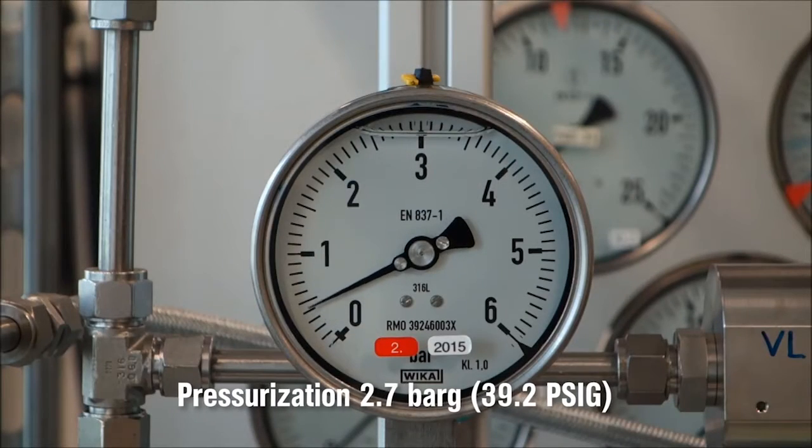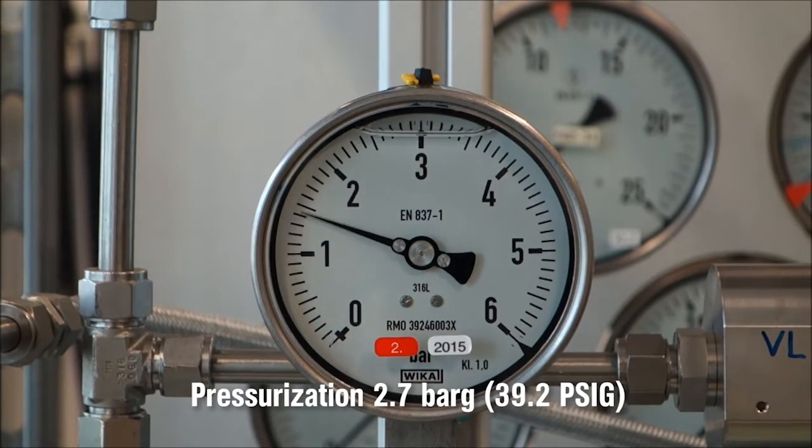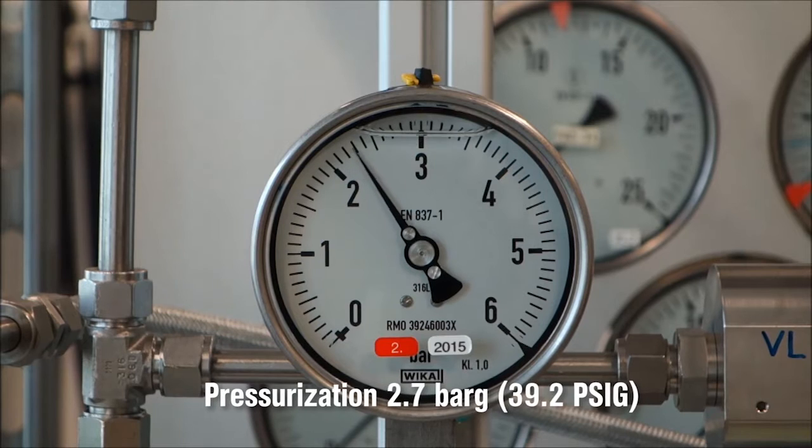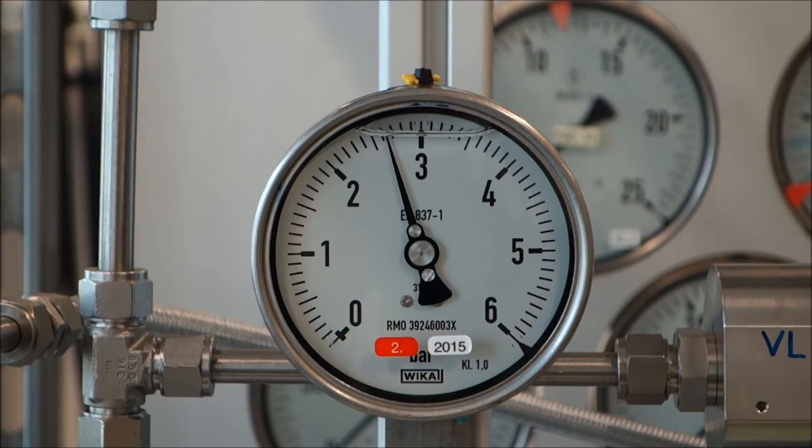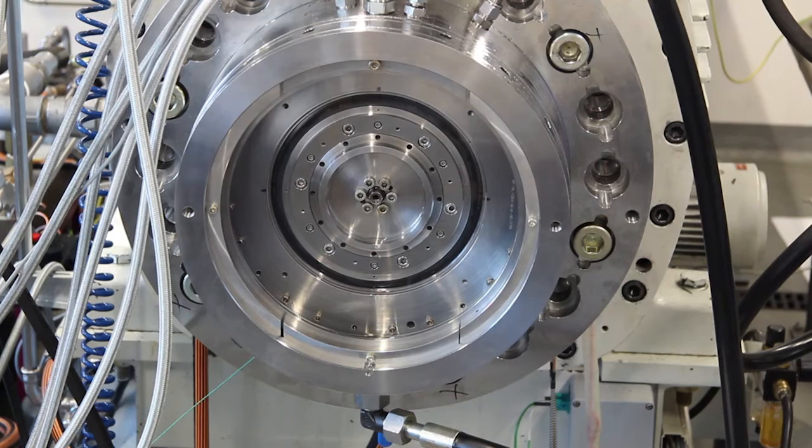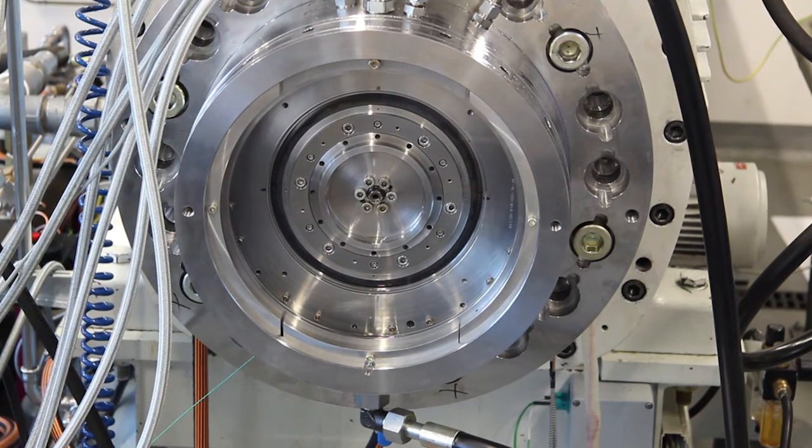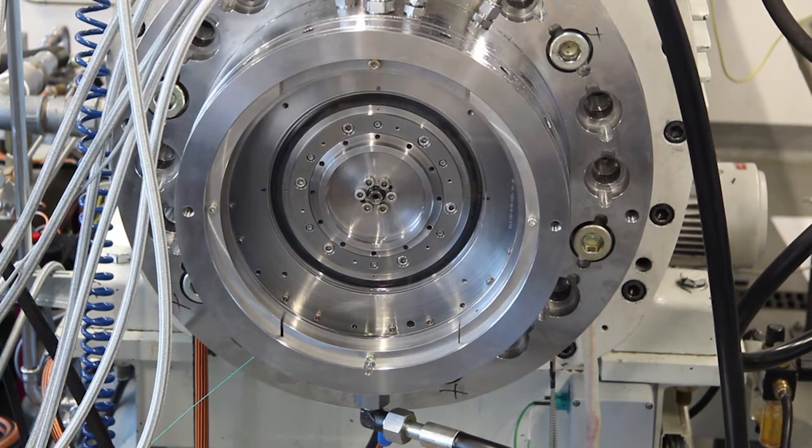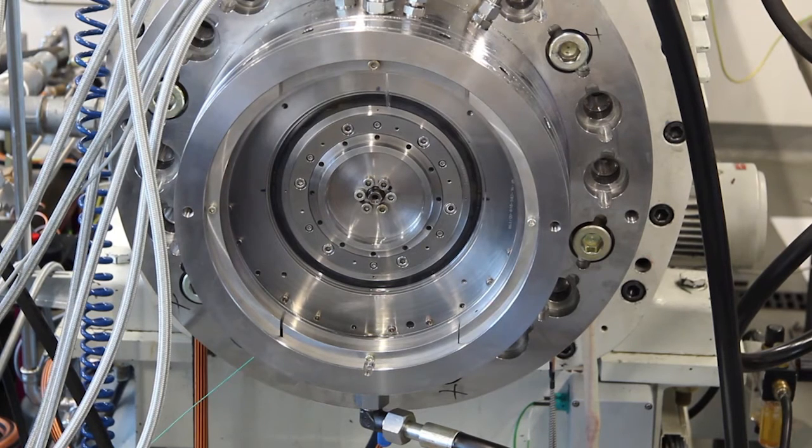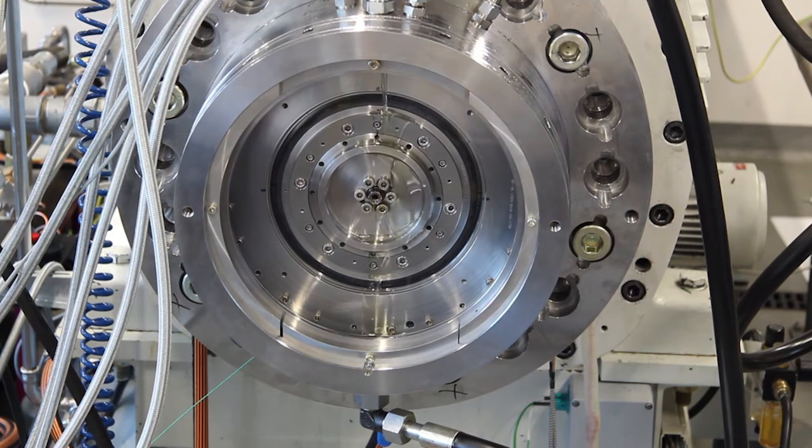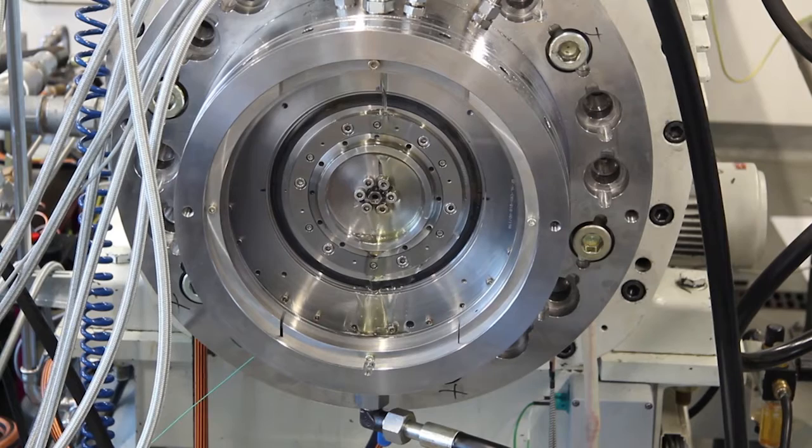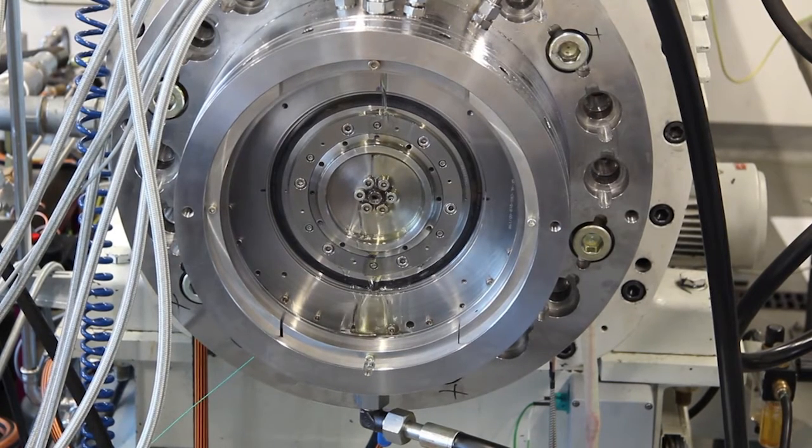The seal first undergoes a dynamic run under normal operational conditions. The processes in the bearing oil housing can be observed through an acrylic glass window. The system is pressurized to 2.7 bar gauge, which is equivalent to 39.2 psi gauge. The oil flow to the bearing housing is 8 liters per minute.